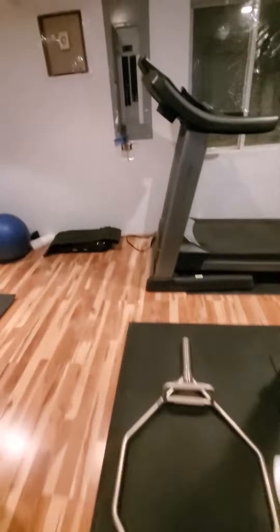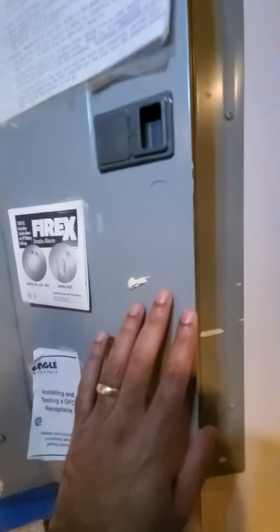The other thing I wanted to show you is the electric panel — your breaker box is right here. 40 amps, double pole, marked for the air con. The furnace is marked with a 15, single, and there are spare slots. Brand is Cutler-Hammer.